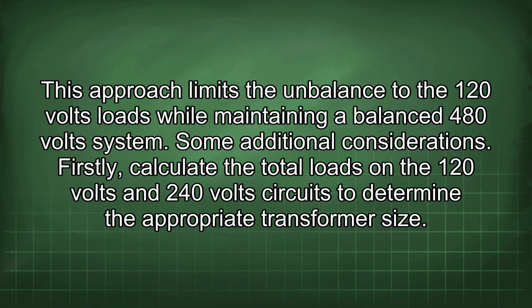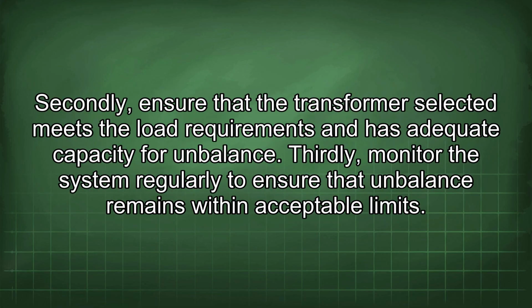Some additional considerations. Firstly, calculate the total loads on the 120 volt and 240 volt circuits to determine the appropriate transformer size. Secondly, ensure that the transformer selected meets the load requirements and has adequate capacity for imbalance. Thirdly, monitor the system regularly to ensure that imbalance remains within acceptable limits.